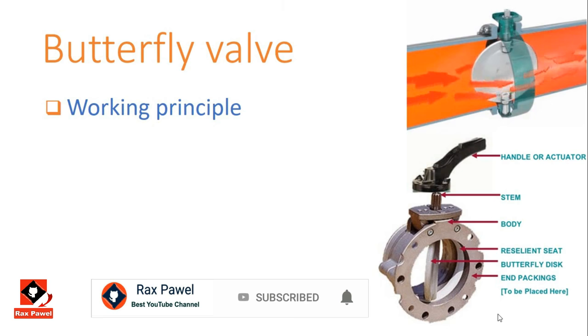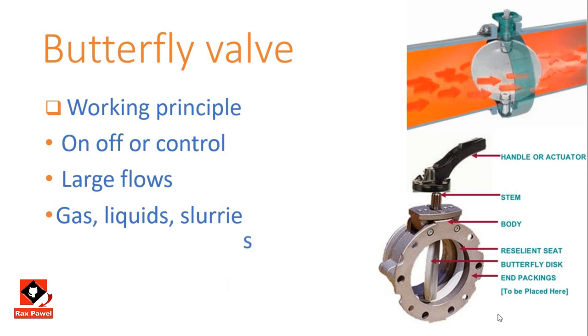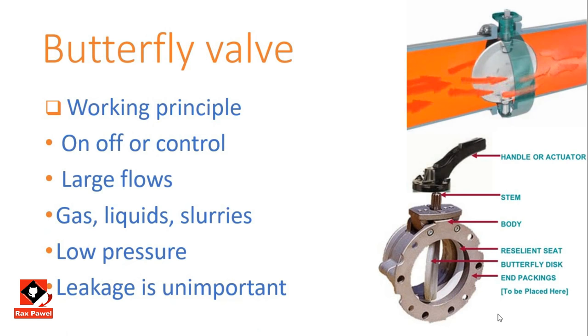Working principle of the butterfly valve: this valve has a rotating disc in the pipe section body, where a stem passes through the disc supported by both ends of the body. It can be used for both on/off and control applications while handling large flows of gases or liquids, including slurries. The butterfly valve is used for low pressure applications where leakage is not critical.